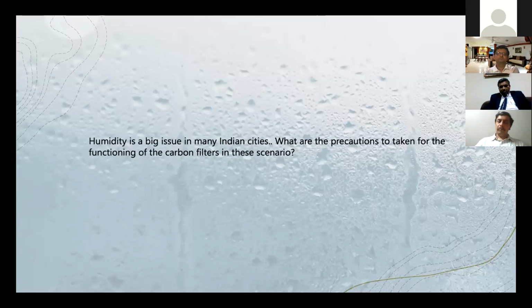I might be very wrong here, but from my understanding, if you're putting charcoal in open petri dishes, I don't think it's going to help with the VOCs. The only thing that it helps with is humidity. Am I right, or am I wrong here? Because the air is not circulating, it's not passing through the filter. Exactly. So it's only going to help with humidity control. Correct, Keshav. Yes, humidity will be absorbed, but as you rightly said, air is not circulated over there, so it may not be cleaning the entire room, only a small pocket. Probably it is getting humidified, and you do not have control on the process.